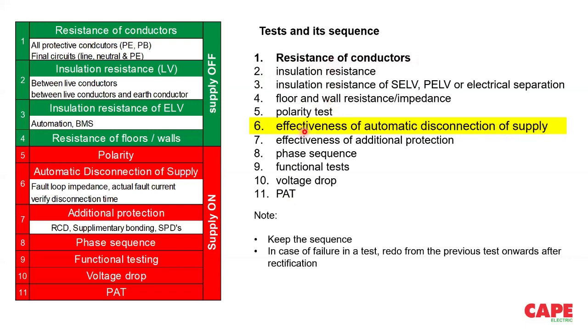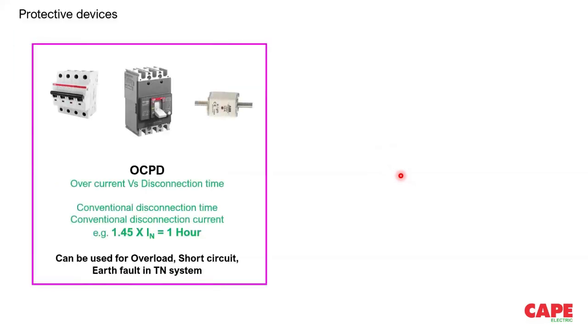Today, we will discuss the protective measure serial number 6 in IS 732 or IEC 60364, or let's say for people from outside India, you can refer to BS 7671, test number 6, effectiveness of automatic disconnection of supply. So the importance of it, how it is carried out and why it has to be carried out is the basic understanding of automatic disconnection of supply. Now, for automatically disconnecting a supply, you need a protective device.